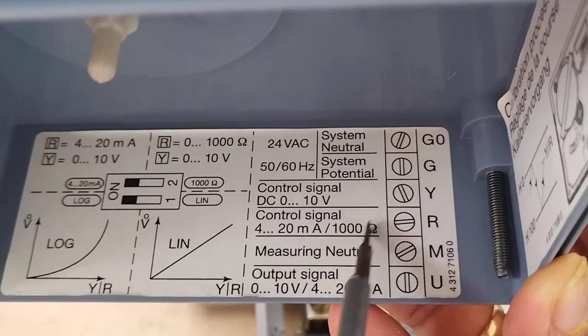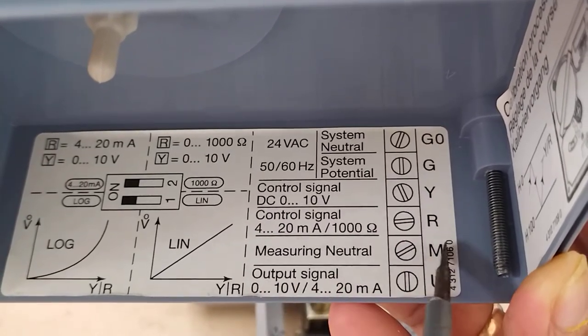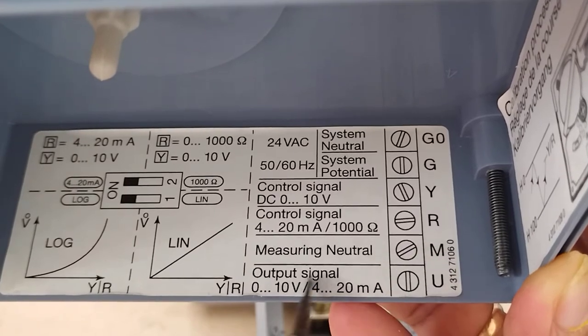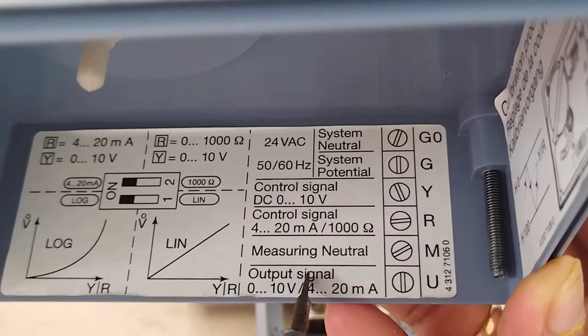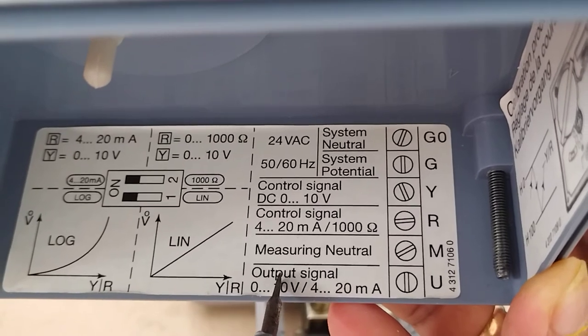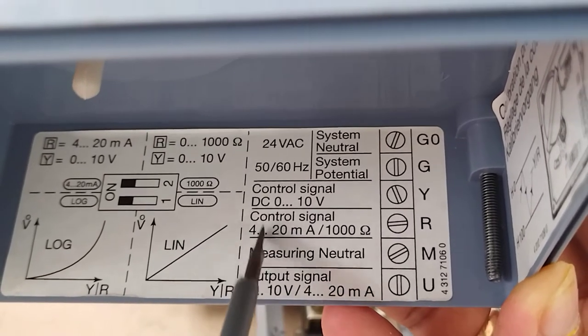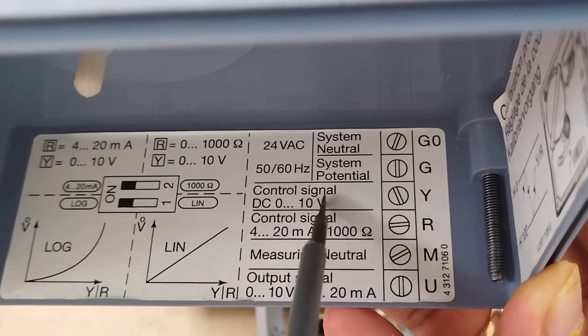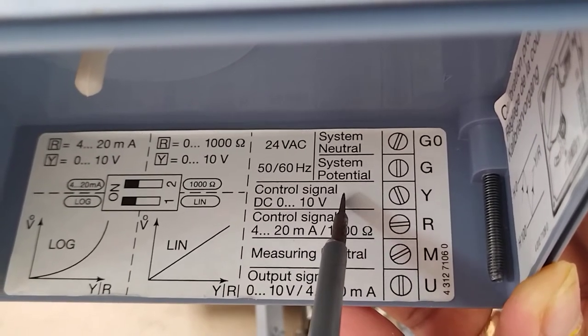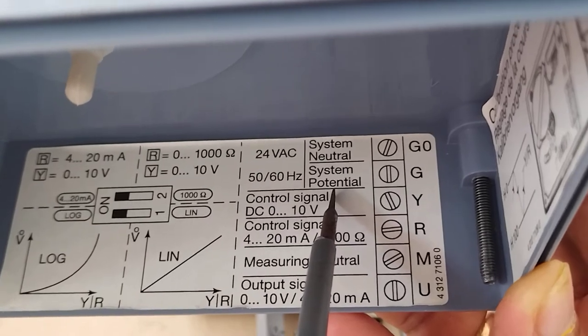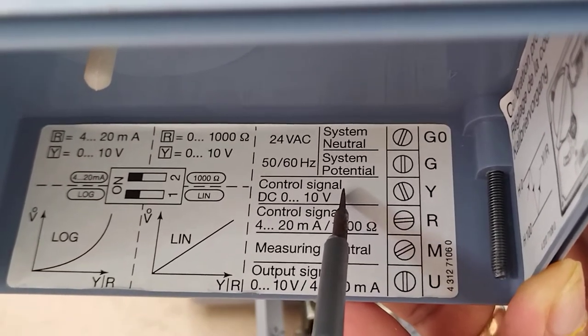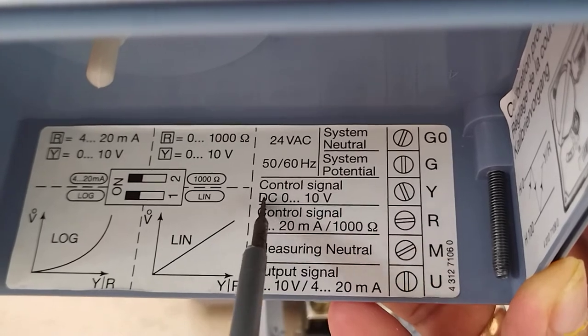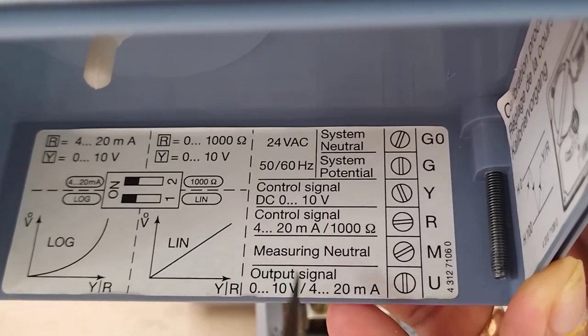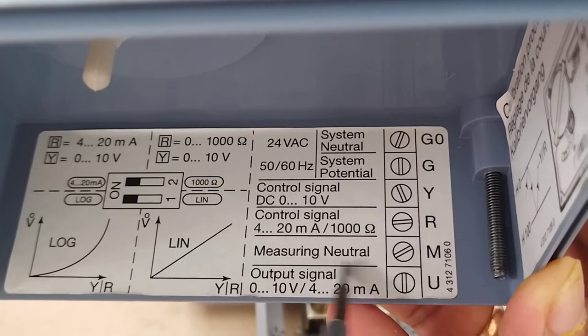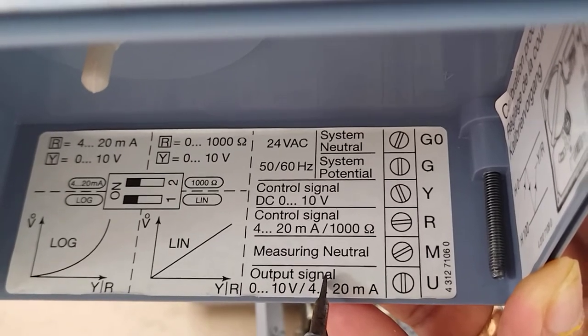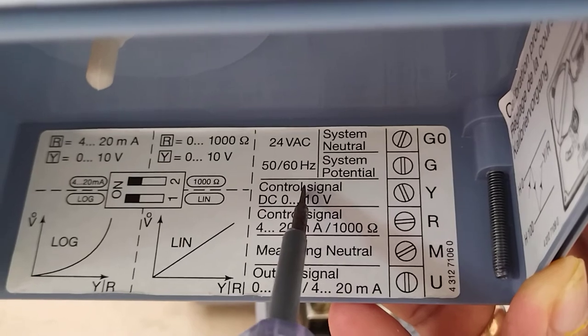Then we have the measuring neutral, and also our output signal. What is this output signal? Actually, it is the feedback status of the valve. Let's say your control signal opens the valve 50%, so you give 5 volts from the analog output module or from the DDC. When you give a control signal of 5 volts, the output signal should also give you 5 volts. So U will be our feedback, and Y will be our control.